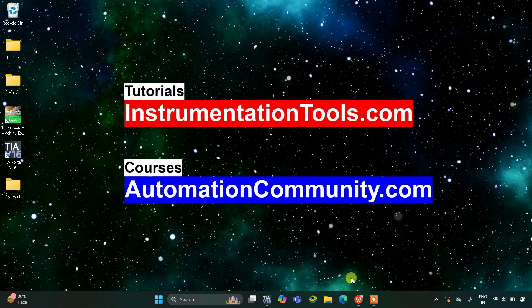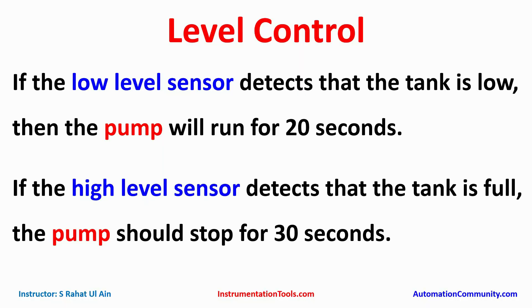Hello everyone, welcome to Automation Community. Today in this video we are going to discuss an example about level control. If the low level sensor detects that the tank is low, then the pump will run for 20 seconds. If the high level sensor detects that the tank is full, the pump should stop for 30 seconds. For this example we will use normally open contacts, normally closed contacts, a pulse timer TP, and a memory bit. Let's move to TIA Portal where we will draw a ladder diagram for this level control example.